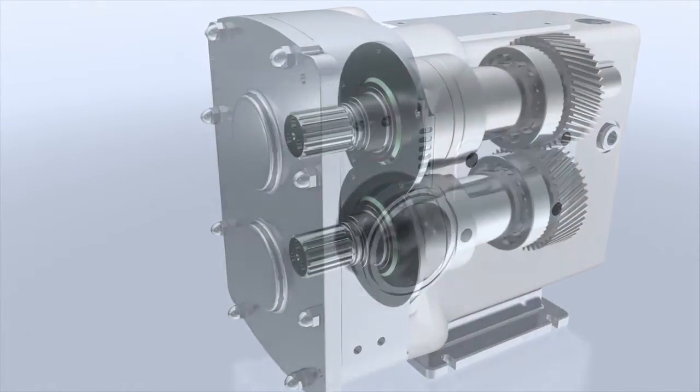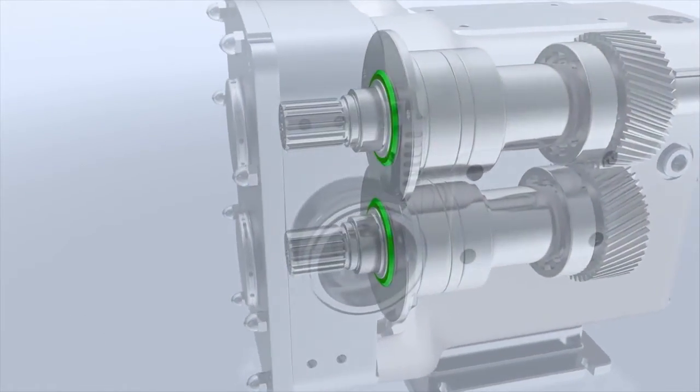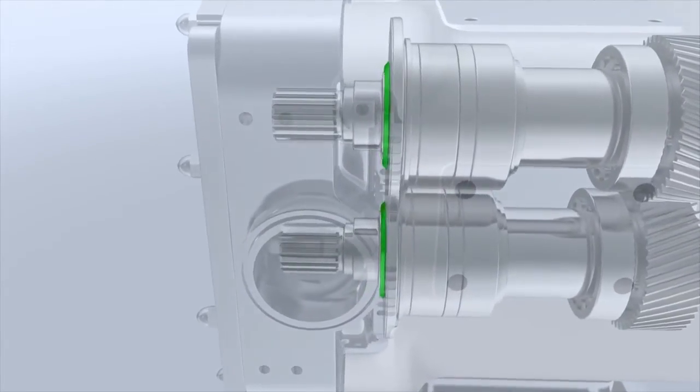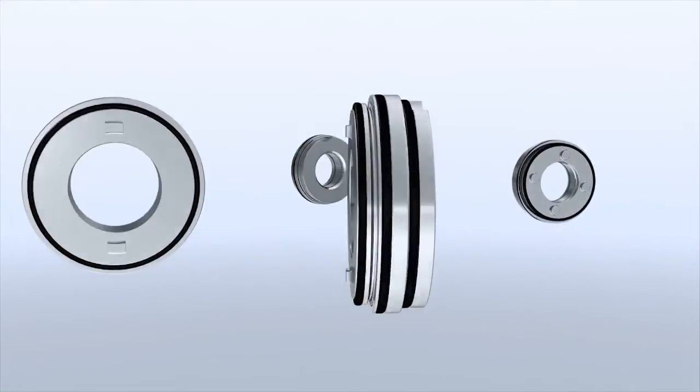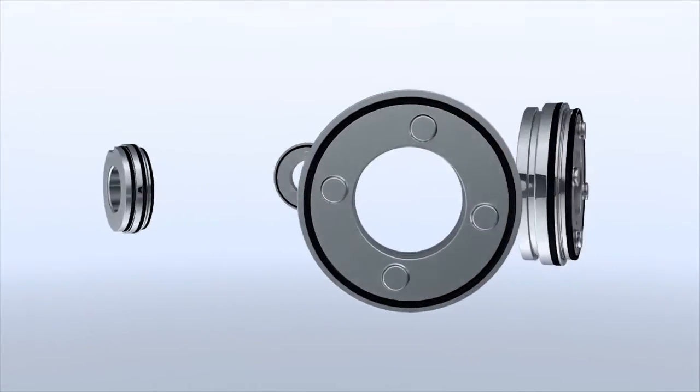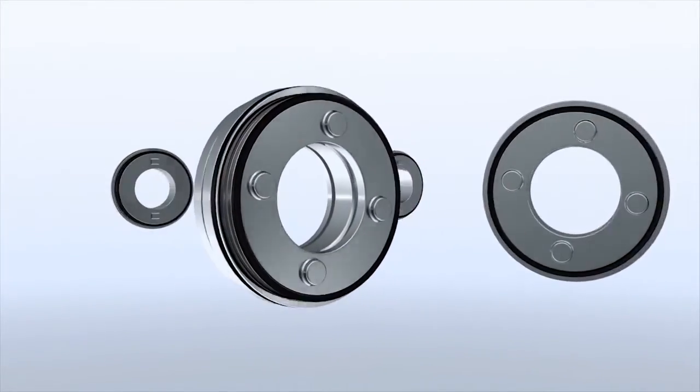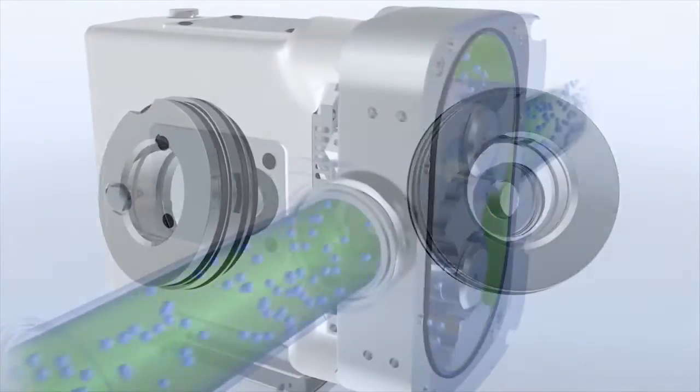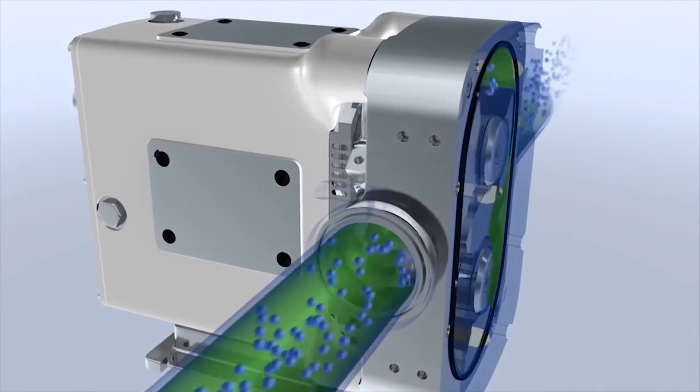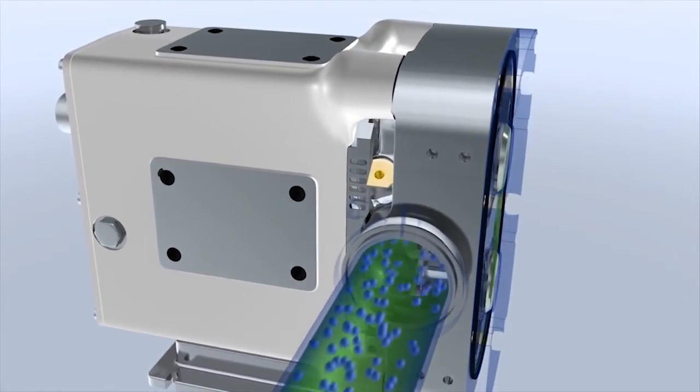The gearbox gamma seal provides greater protection, preventing any possible intrusion under heavy washdown applications. Seal options include single o-ring, double o-ring, single mechanical, or double mechanical seals. A broad range of seal materials is available, and flush drillings are standard, allowing for further seal option flexibility.